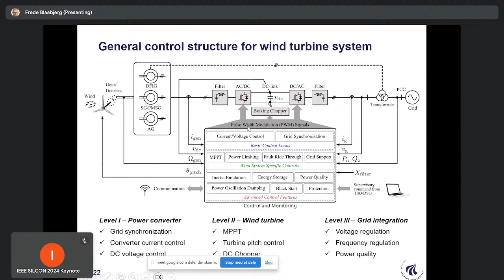Then we have a next level of control where we control the power. We can support the grid, but we are also able to optimize the energy harvesting from the turbine, as well as limit the power when it's operating. Those have a little lower dynamics. And then there are a lot of new features which are interesting to have, like inertia emulation, energy storage, black start, and so on, which run with a little lower bandwidth in terms of serving their purpose. But there's a hierarchical control structure which has been applied for many years, and each converter has very fast control loops in order to protect it and to serve its function.